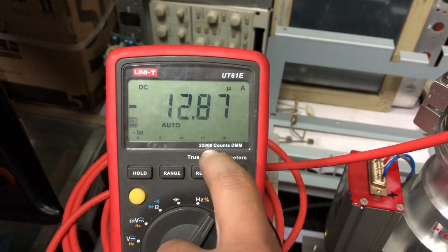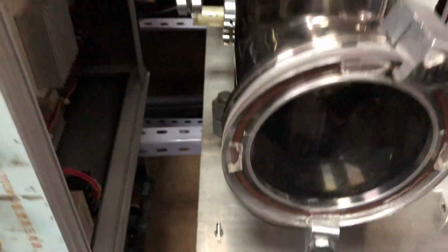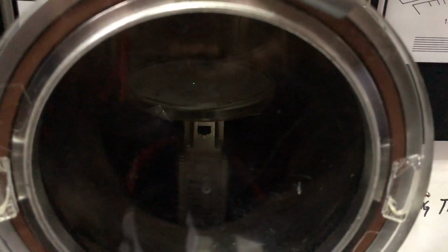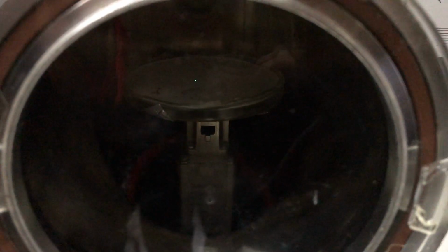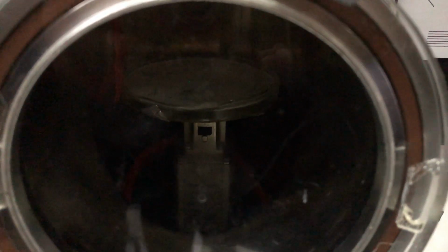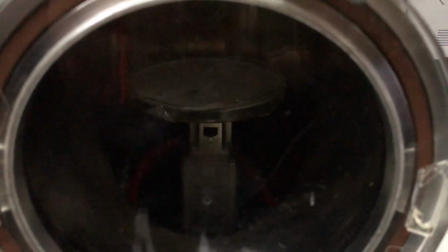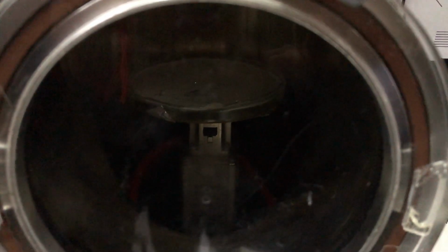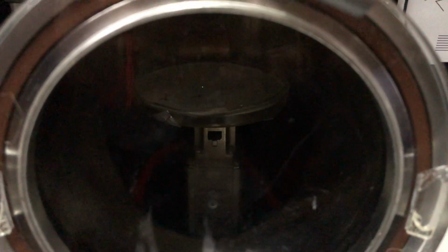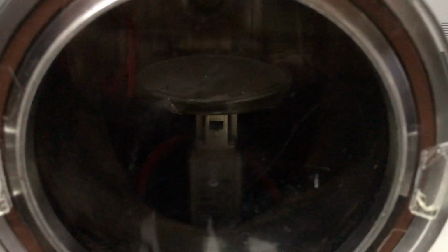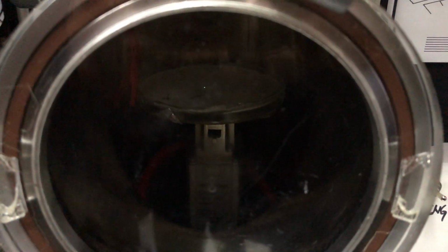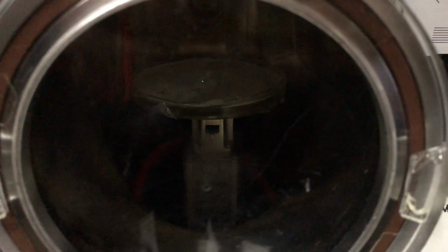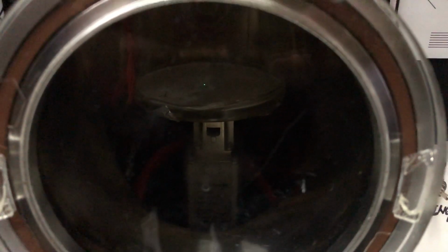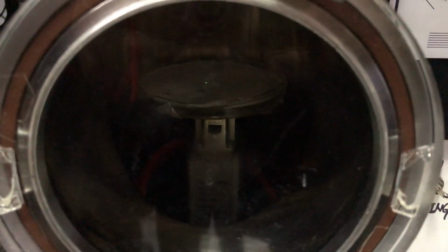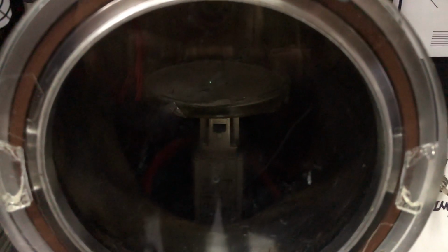So turning down here, we are looking at the light spot. Okay, now we are turning down the high voltage, and you can see the spot has disappeared. Okay, now we are increasing the voltage, and you can see the spot is coming back. And if we increase it, now you can see it's much brighter. Okay, so about 4 kilovolts is the limit on this system.